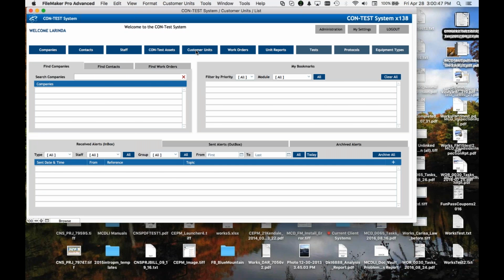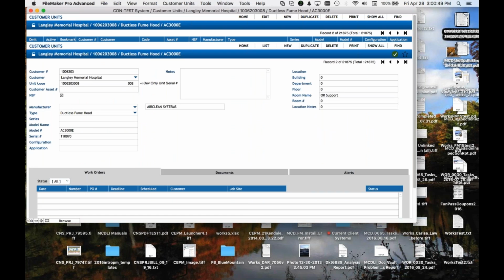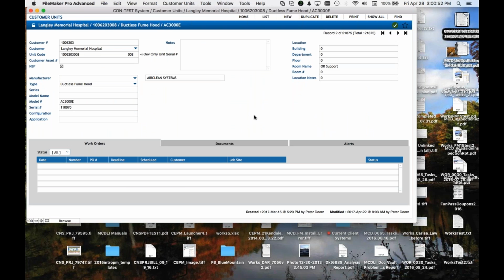Yeah, the access opening. It'll never change on that unit, ever. It's always going to stay the same. So those specific kinds of values could sit in here, right? So that they don't have to be entered over and over again. No one has to check them. Any of those standard numbers could sit with the Airflow unit. The airflow ranges will be the same as well. I mean, the airflow ranges are set in stone. They are not movable. So same kind of thing. That's data that you could have in there.